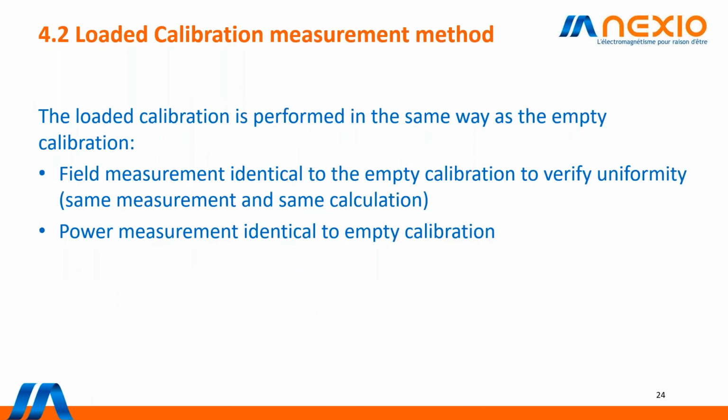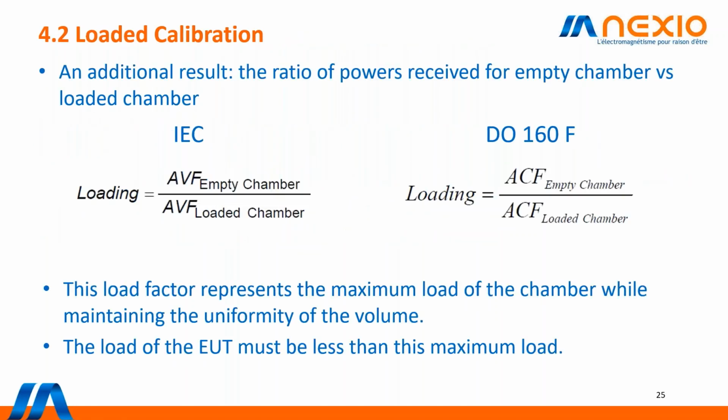So the measurement method is exactly the same as the empty calibration, with two measurements, E field and power. And the results are similar to the empty calibration with one more calculation, the ratio of power called loading.